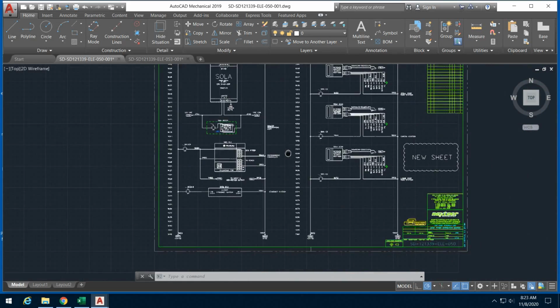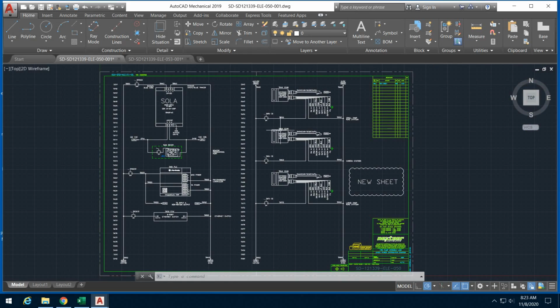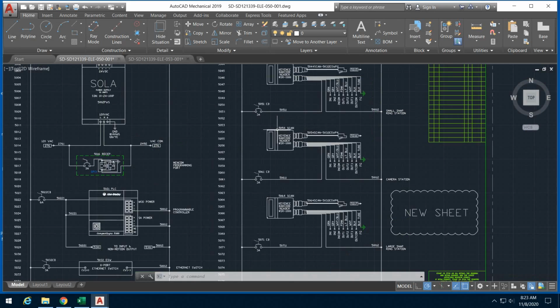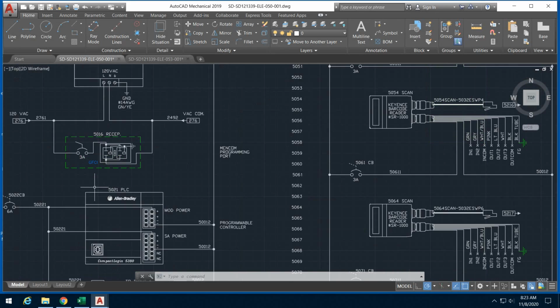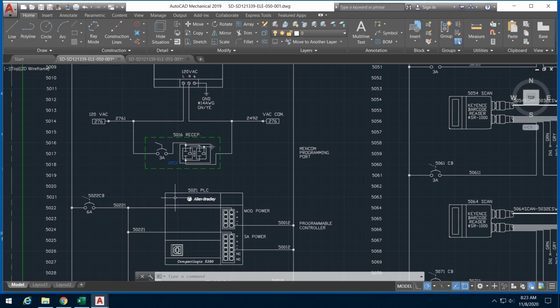I'm going to come out a little bit. You can see the equipment, like this PLC is 5021 PLC. Well, on the machine itself, there would be a label, a printed vinyl label that says 5021 PLC on or next to this 5380 PLC. And that would tell me, hey, it's on sheet 50, line 21, that's how and where I can find this PLC in the electrical print.